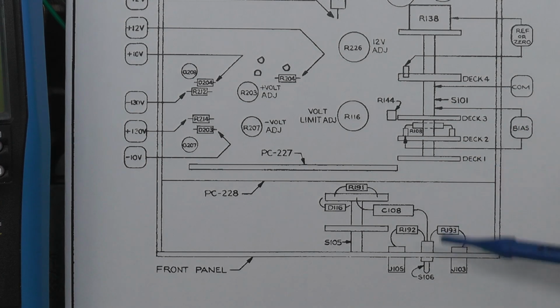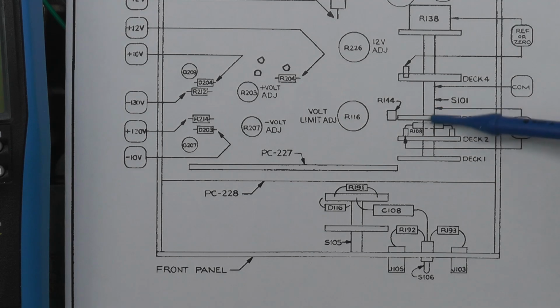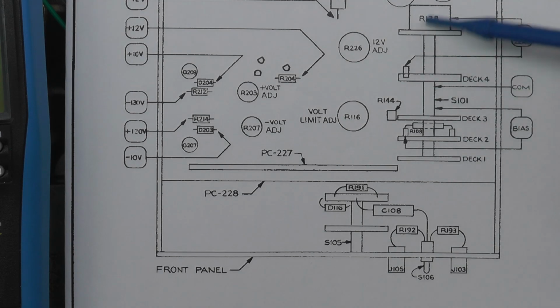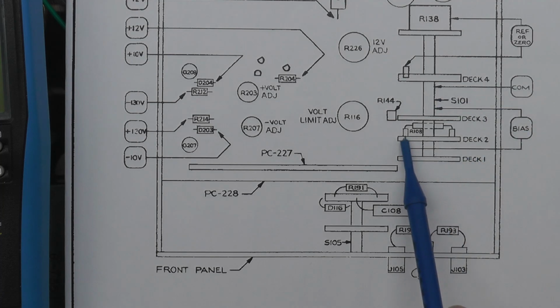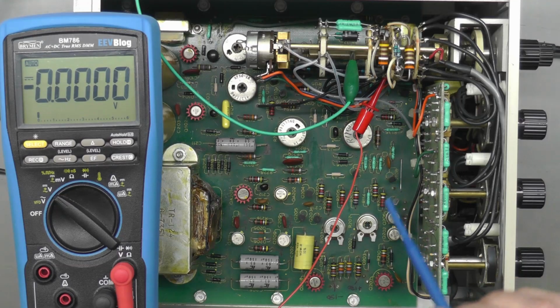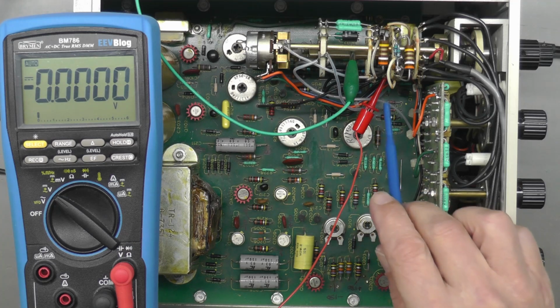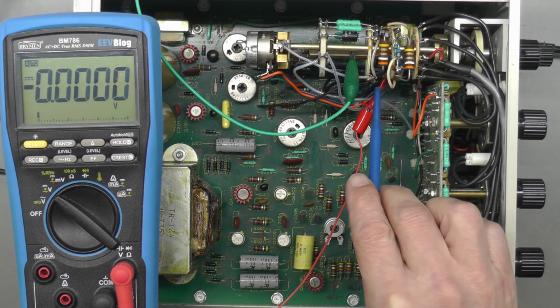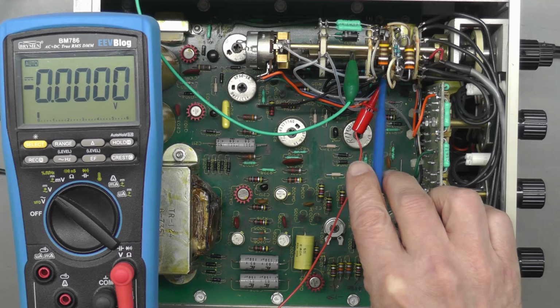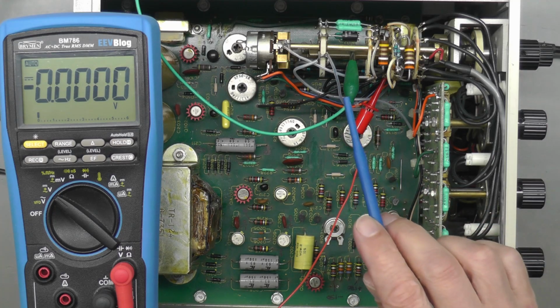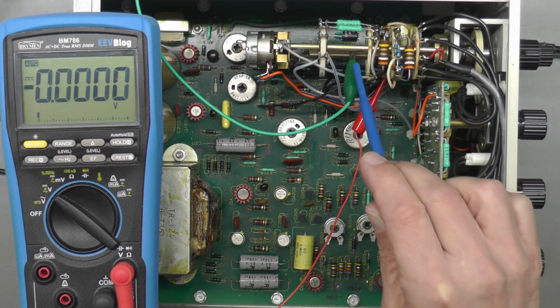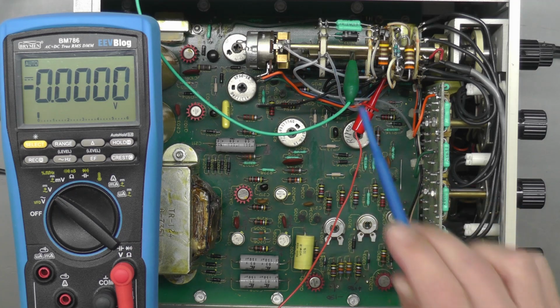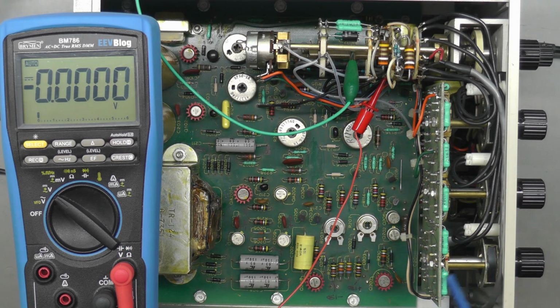Here's figure 16, showing the bias adjustment. You're supposed to connect across the shaft of the range select switch, which is your common, and this end of R108. So there we go, I've got my positive lead connected to R108, on the underside of that range selection switch, and my negative lead for the meter on the shaft of the range selection switch. Voltmeter's hooked up, and we're all ready for power up.